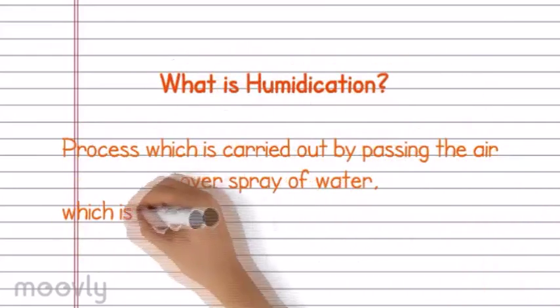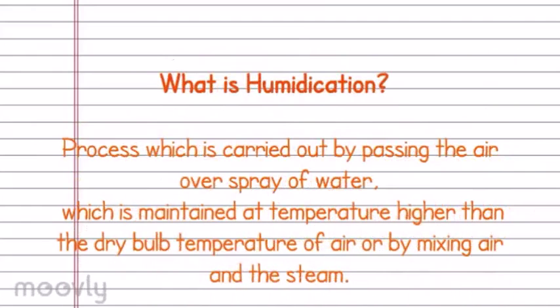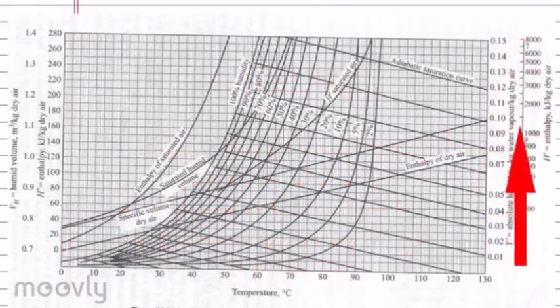The process in which the moisture or water vapor or humidity is added to the air without changing its dry bulb (dB) temperature is called the humidification process. This process is represented by a straight vertical line on the psychrometric chart starting from the initial value of relative humidity, extending upwards and ending at the final value of the relative humidity.